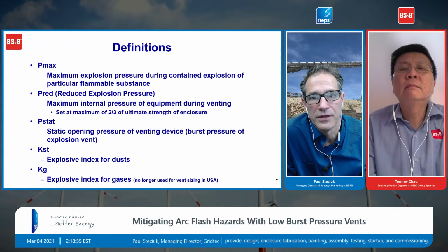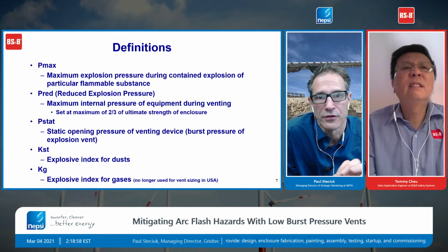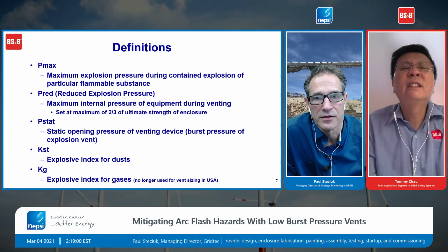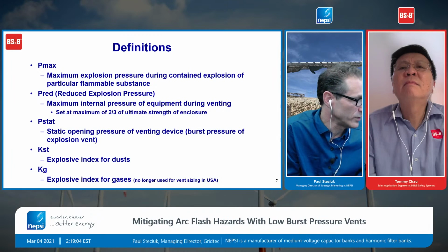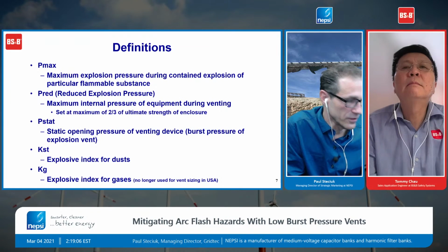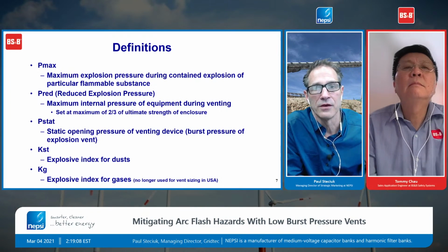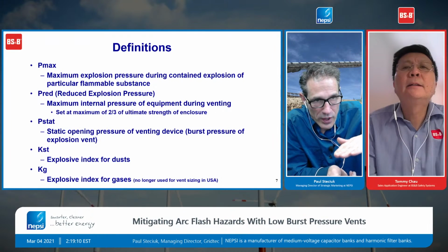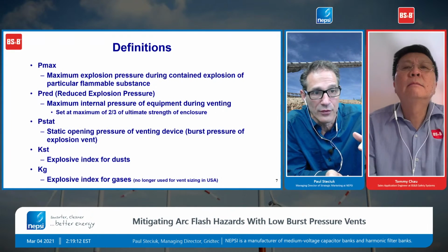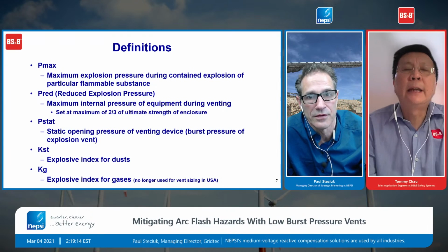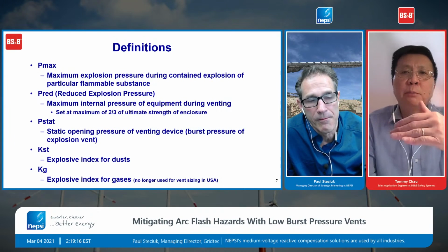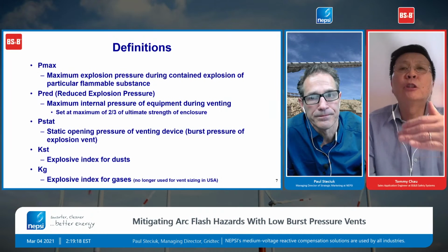The P reduced, the P red, in other words, is the maximum internal pressure in the equipment during the venting. So if we had applied this low burst vent into our system, we're saying the pressure is going to rise to that value, basically, to that reduced value. Yeah. And below the P red is the activation pressure of the explosion vent.